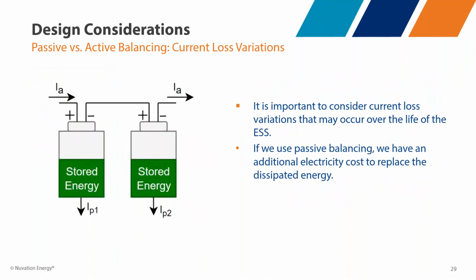It's also important to think about current loss variations that occur over the life of the energy storage system. If we use passive balancing, we have a little bit of additional electricity costs to replace the energy we're dissipating as heat, so that needs to be factored into the efficiency of the system.